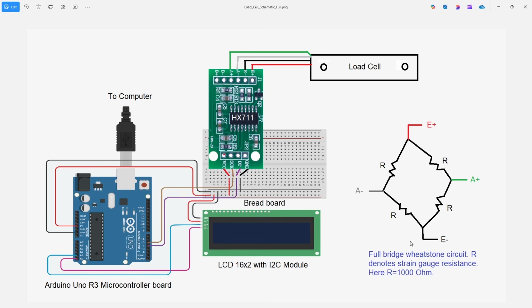So there are 4 wires which are coming out of this particular load cell. E plus and E minus are used to energize the Wheatstone bridge. In this particular experiment, 5 volts is being applied across E plus and E minus. Now the 2 strain gauges on the top, one of them will be here and another over here. The strain gauges on the bottom, one of them will be here, another will be here.